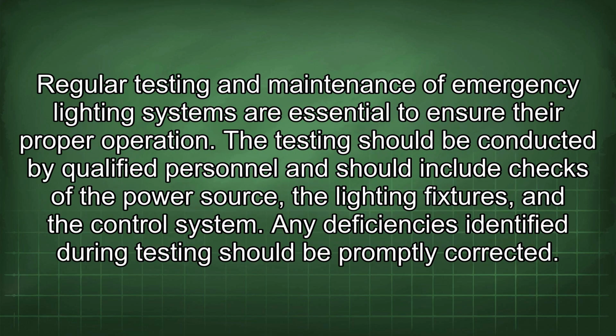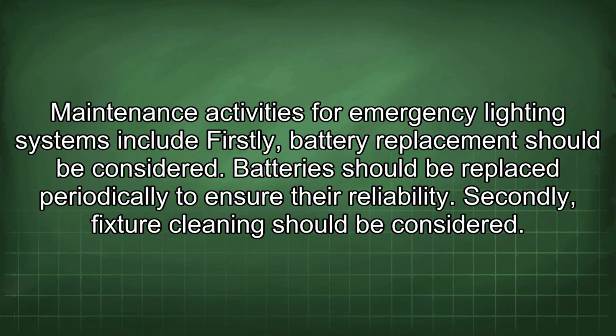Regular testing and maintenance of emergency lighting systems are essential to ensure their proper operation. The testing should be conducted by qualified personnel and should include checks of the power source, the lighting fixtures, and the control system. Any deficiencies identified during testing should be promptly corrected. Maintenance activities for emergency lighting systems include, firstly, battery replacement. Batteries should be replaced periodically to ensure their reliability. Secondly, fixture cleaning should be considered.